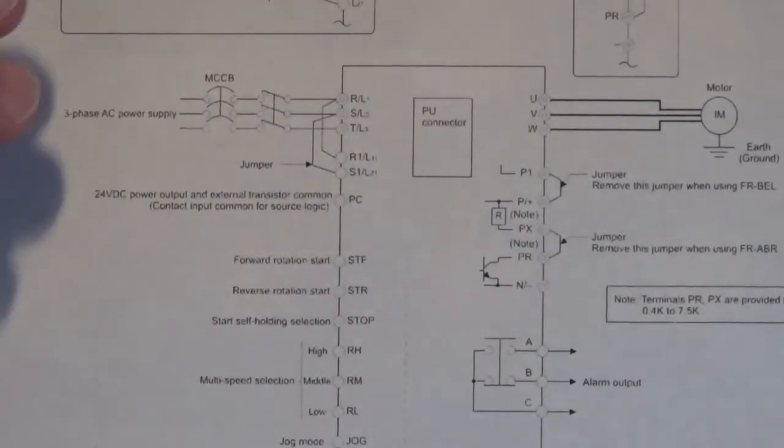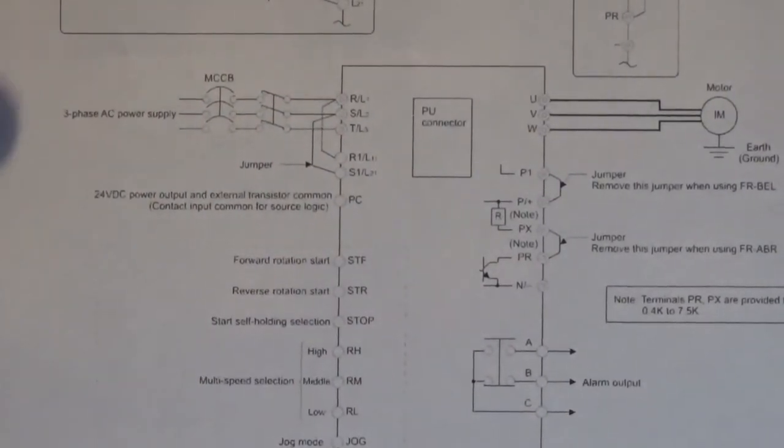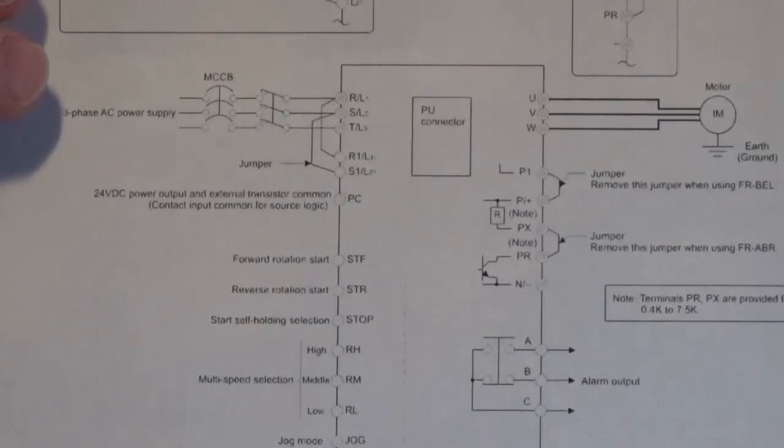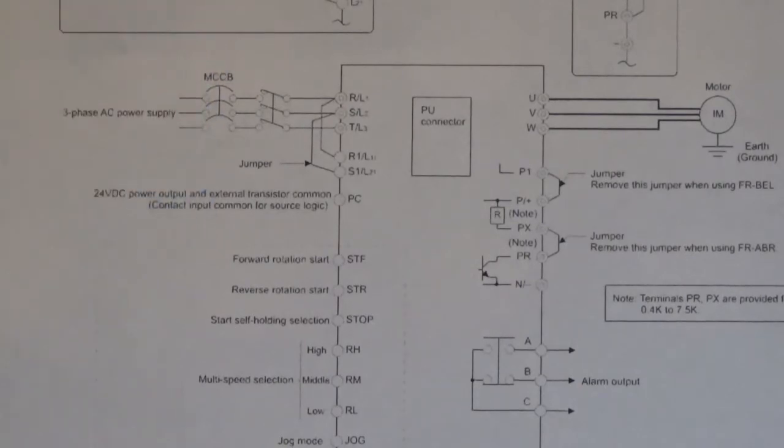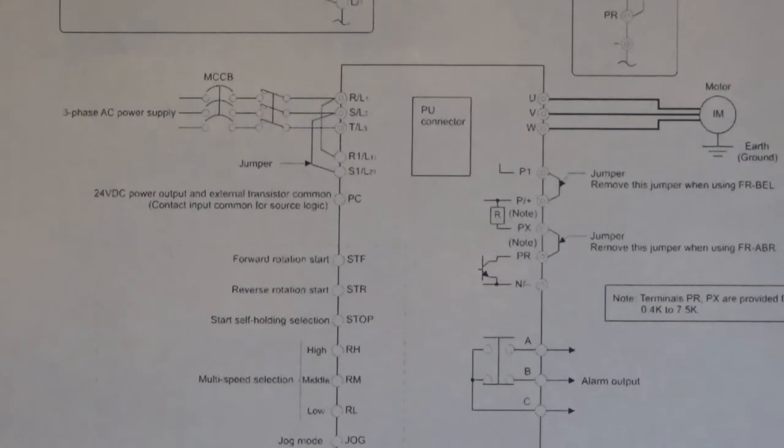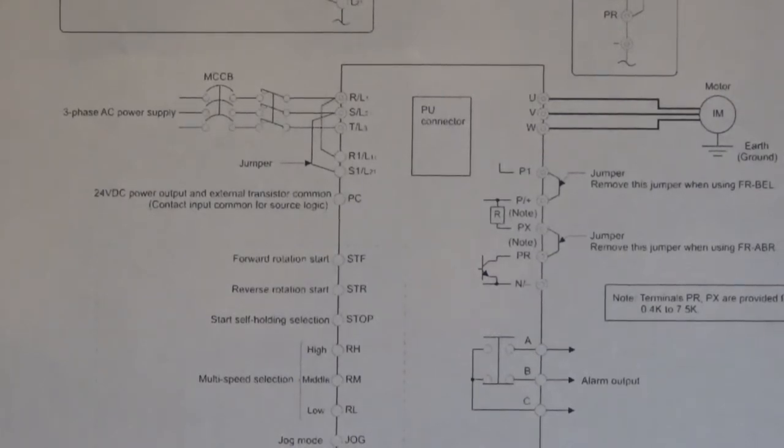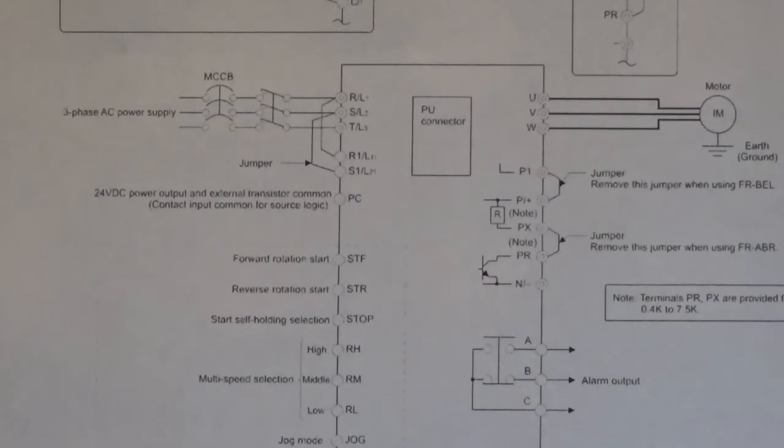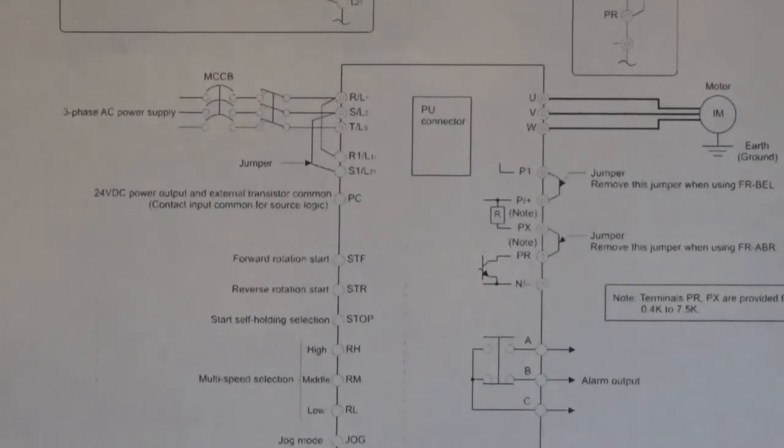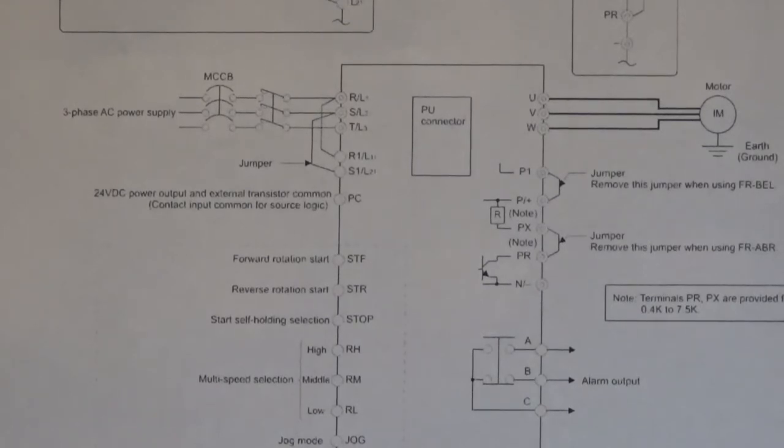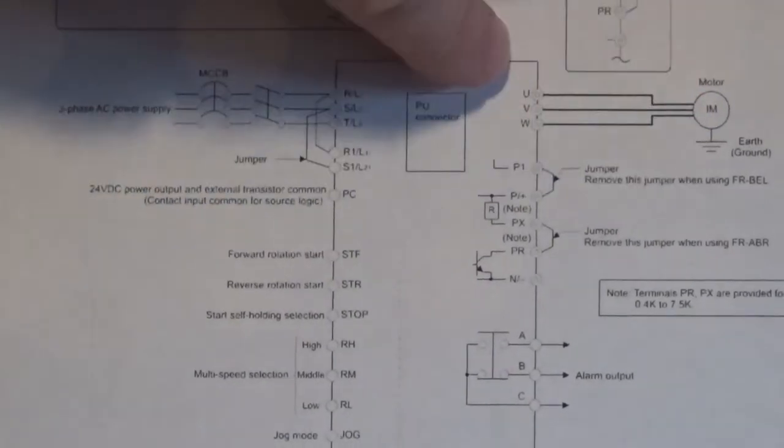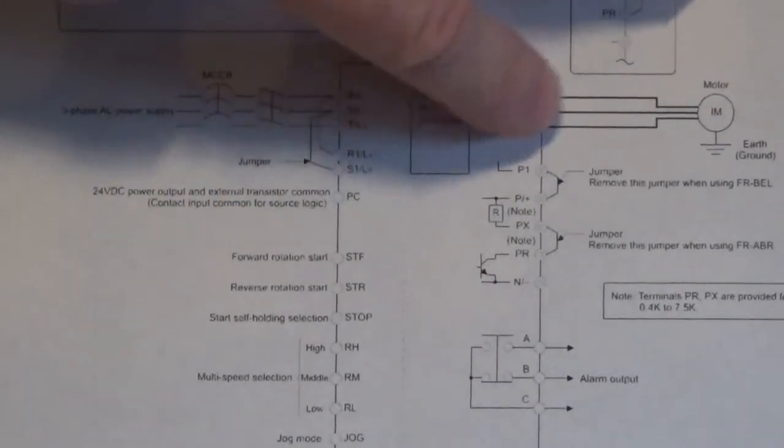Now on this drive, it was 380 volts AC to 480 volts AC. You check the data plate on your drive because some of these drives are 220 volts AC. And if you put, don't do it, if you put 380 or 480 volts AC into a 220 volts AC drive, well you might as well take it out to the trash because it's gone. It will explode.